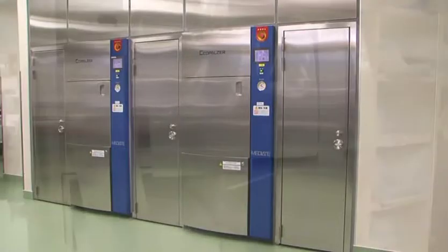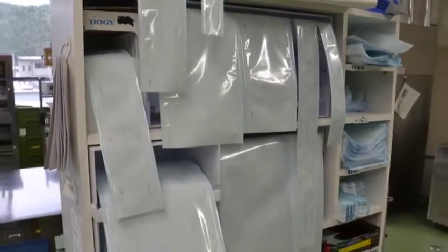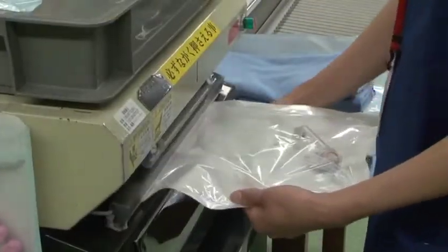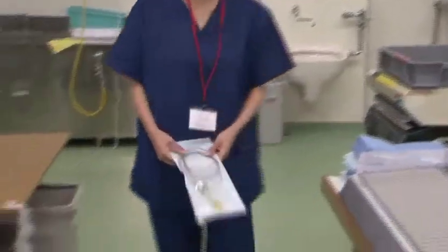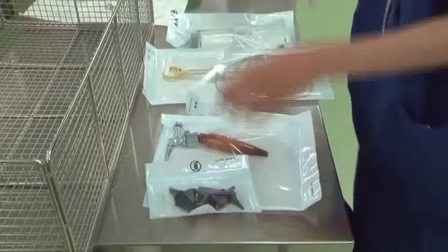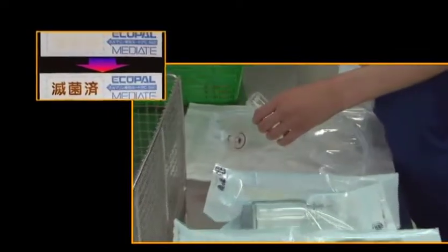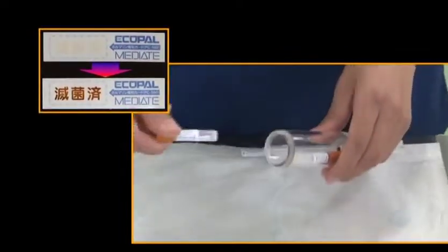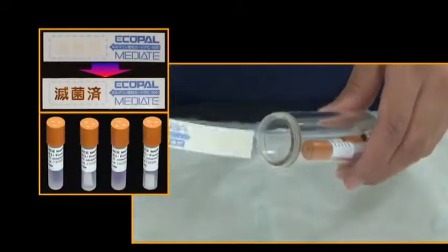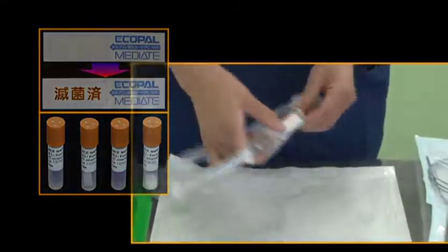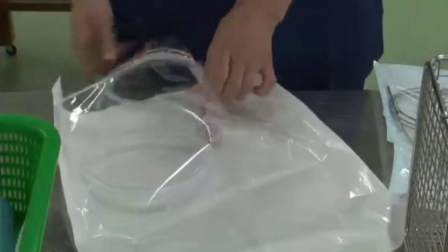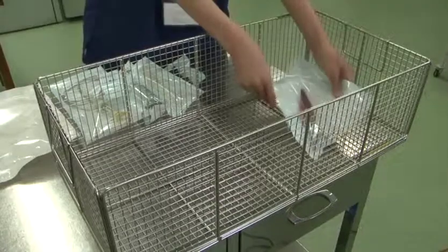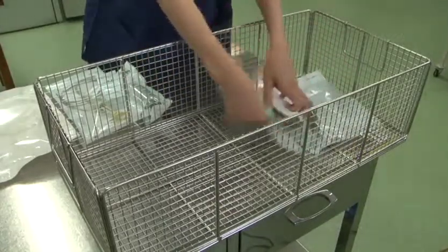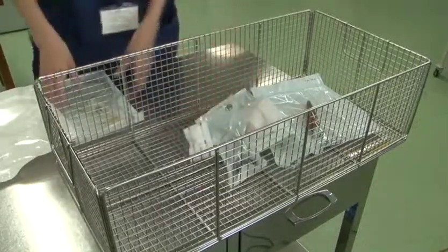Now, let me show you how to actually use ECOPALZER step by step. First, you put the medical instruments in the sterilization bag. At the same time, set the chemical indicator, and if necessary, also the biological indicator into the PCD to check the effect of the sterilization. Next, place the sterilization bag in the attached basket. In doing so, be careful not to overload the basket with too many sterilization bags.